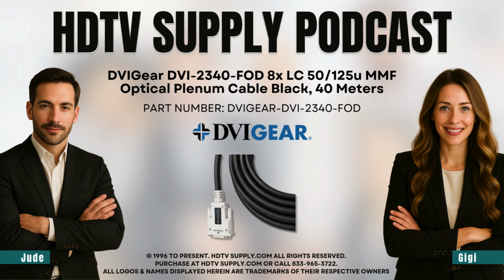A cheap PVC jacket on a standard home cable acts as highly combustible fuel if a fire breaks out in a server room. And because that cable is sitting in the plenum space, any toxic fumes and thick black smoke would get sucked straight into the building's ventilation and pumped into every other room, spreading instantly and rapidly poisoning the air supply of the entire facility.